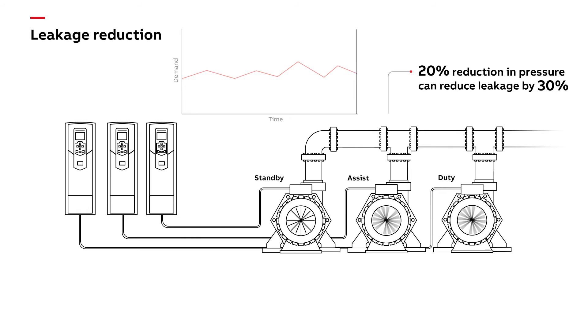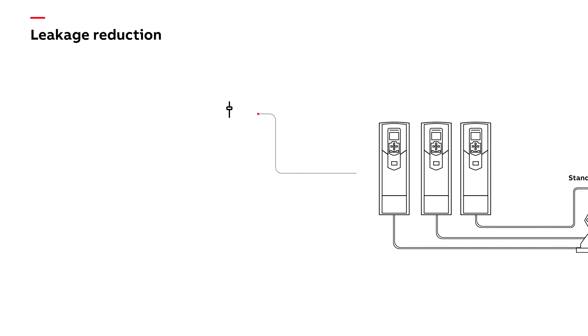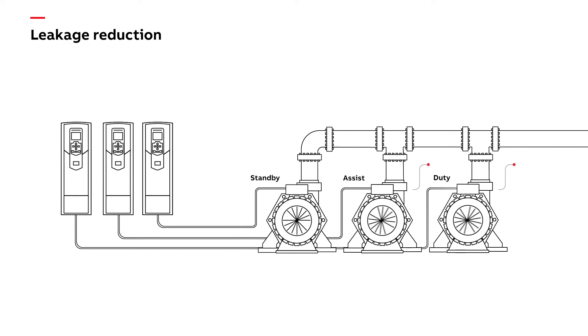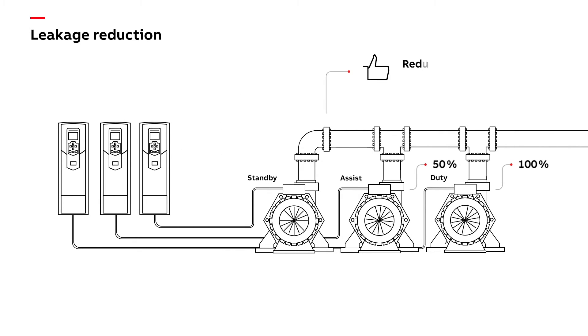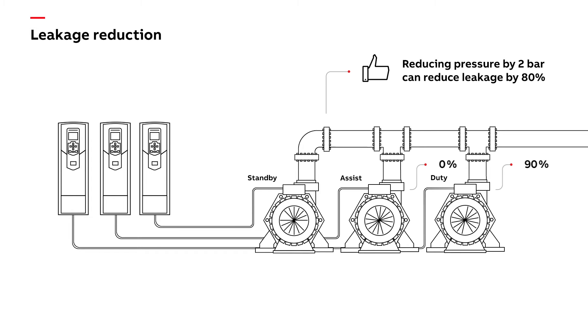Modern drives are easy to use and making adjustments is not difficult. Settings can be approximately adjusted at installation and then fine tuned over time. A system providing 5 bar during the day, for example, could be set to automatically reduce to 3 bar overnight using inbuilt control.